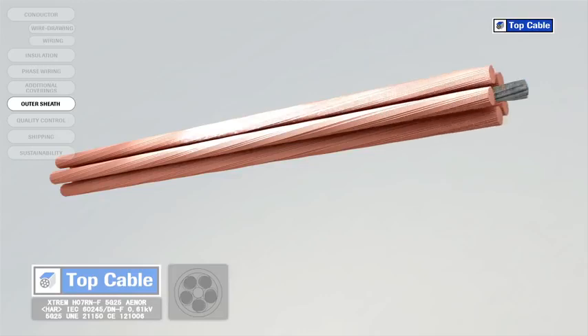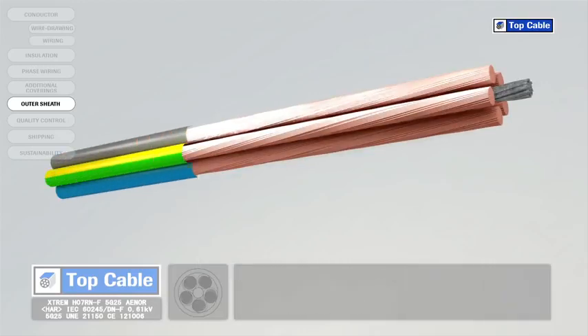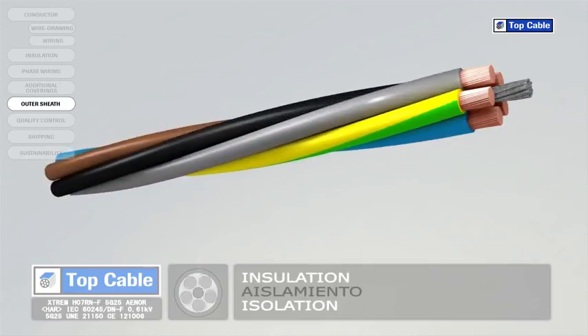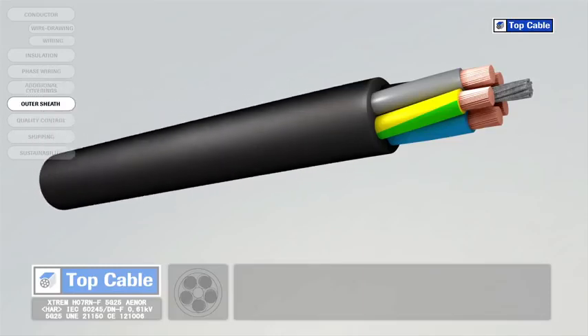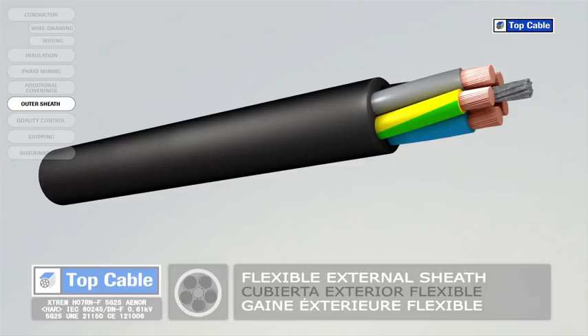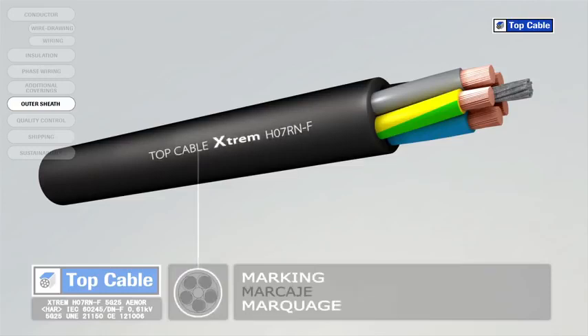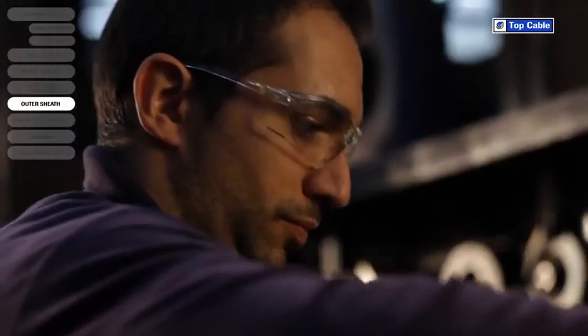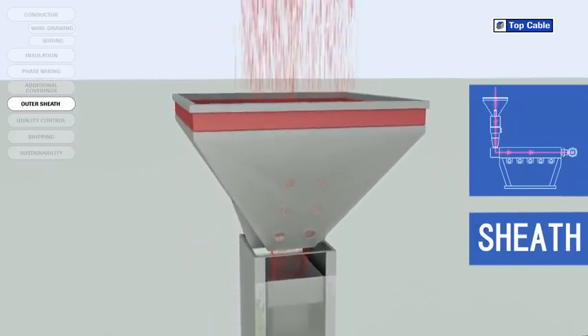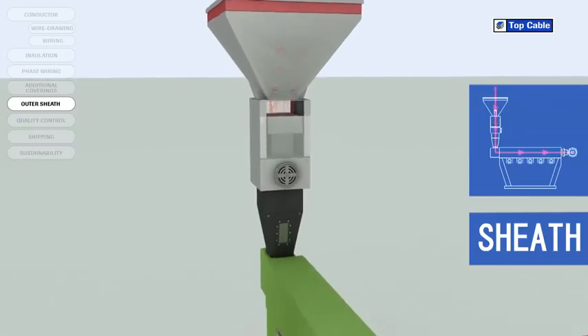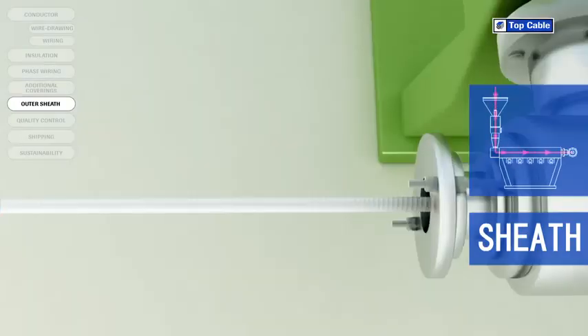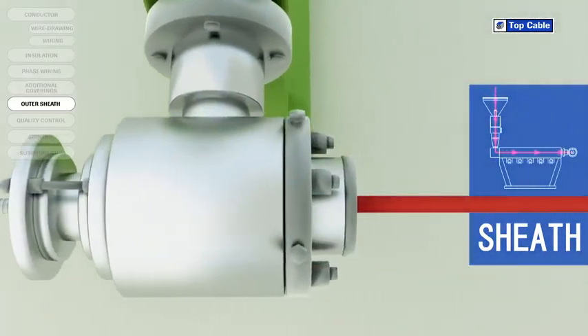Cables usually have an outer polymer covering for protection, called the outer sheath. The sheath protects the conductors and their insulation from external elements which may change their electrical properties, such as moisture. It also protects them from mechanical aggression during installation. As with the insulation, the outer sheath can be made from a thermoplastic or a thermosetting plastic, applied via extrusion at high temperature. The sheath material varies depending on the required protection level, the final flexibility of the cable, the work environment, etc.